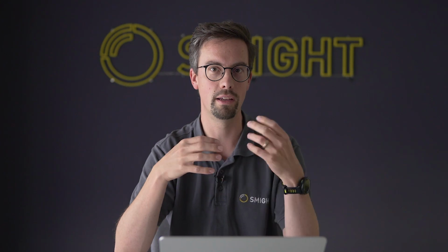So three levels: one level of estimation with a reasonable level of accuracy. You can improve that accuracy with the voltage sensor, and then you can get a direct monitoring point. And it's really up to you as the network operator to decide which one makes sense to operate where in your network. So where a rough estimation is more than enough, that would be the place to use it, but maybe where you're closer to the edge of the operating envelope, it may make more sense to monitor the transformer directly with accurate measurements.